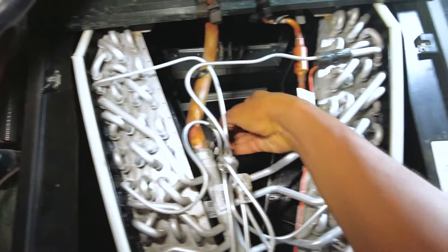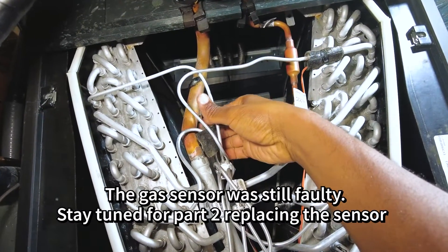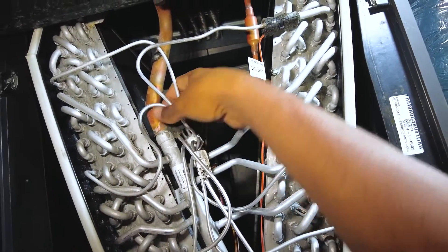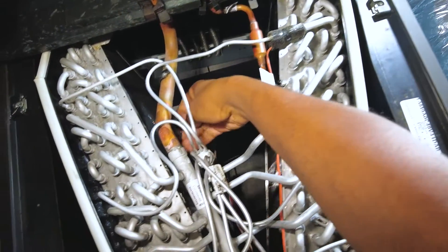Let's see if we can find this gas sensor — it's going to be here on the suction line. Here we go — it just simply fell off. I still don't know how it got 100 degrees though. I'm going to place it back just in case; it's reading 100 degrees and it should have never been reading that high.